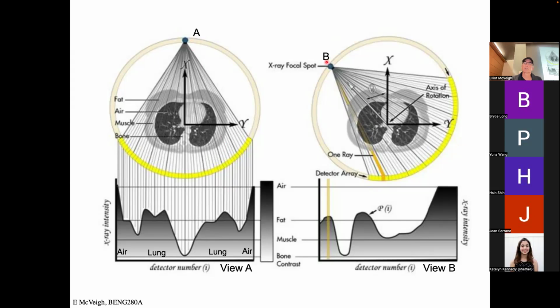Now we'll rotate the source, and the plot of the absorption just shifts along with that rotation, such that now if I look down through here and say, where do I get a deep attenuation of X-rays? It's wherever I'm hitting this spine usually. It gives me the deep attenuation over here. So that feature moved over to that position. And now here I have a lot of beams that are just hitting the detector clean. They're not passing through the patient at all. So I have many that are at this baseline value of X-ray fluence.